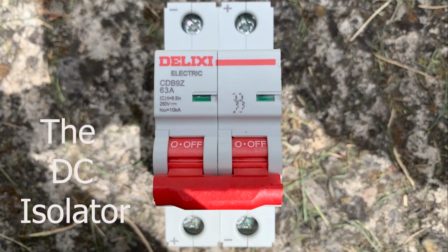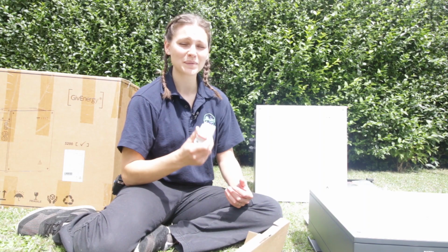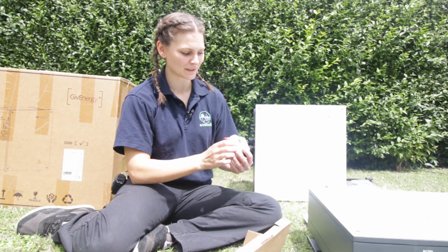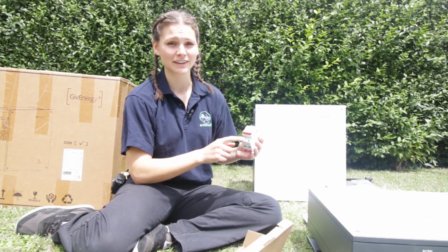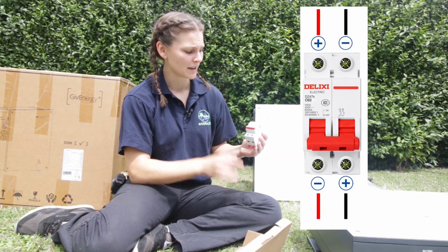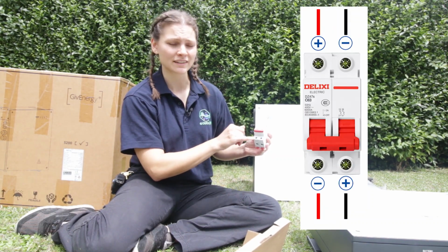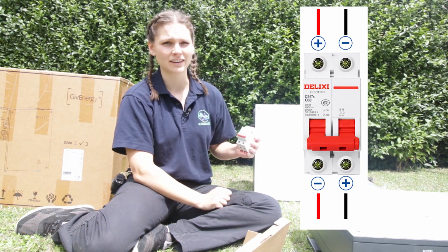This is a DC isolator, and it sits between the inverter and the battery. This will isolate the battery from the inverter. Only one of these is required on a multiple battery application. Be warned, the isolator is labelled positive on the top left and bottom right. You don't cross the cables over in this one. Both red wires go to the left hand side, both black wires go to the right hand side.